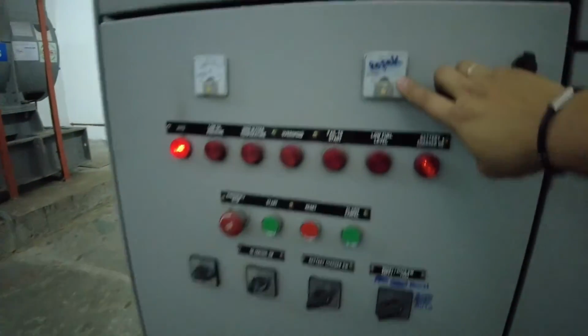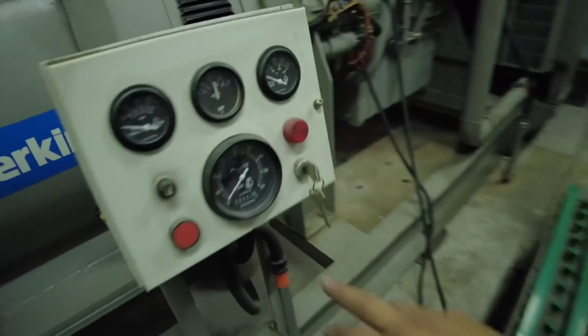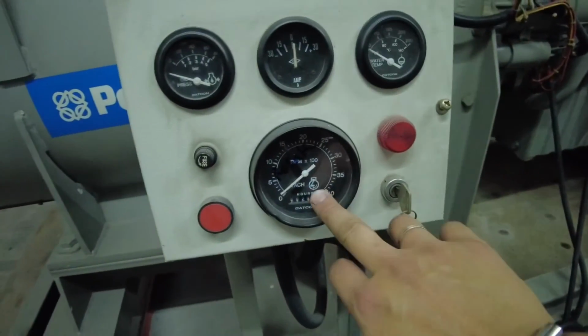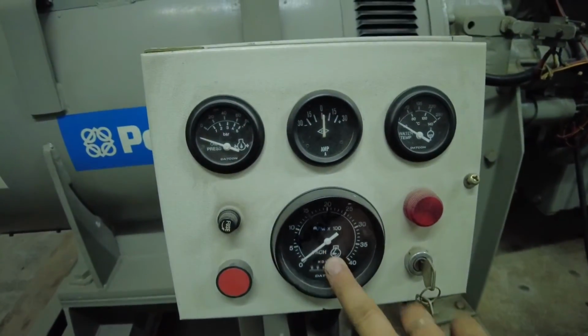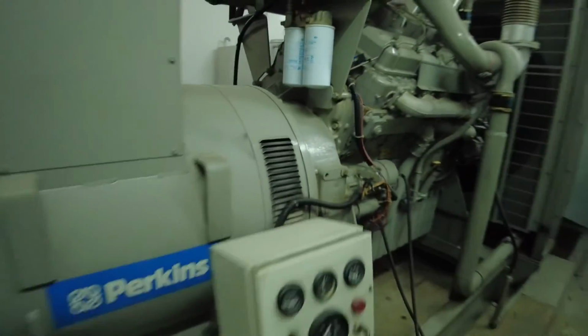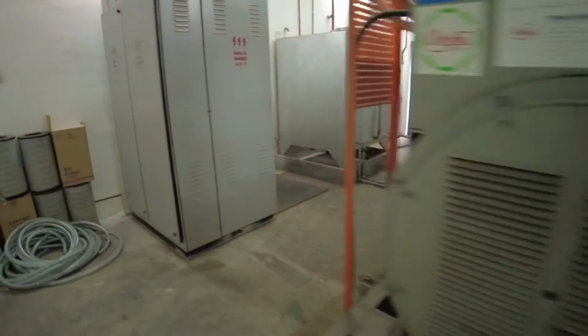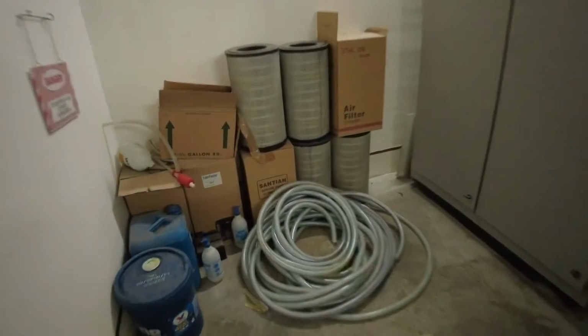After the genset stopped automatically, we found two items faulty. First thing is this voltmeter is faulty. And also this RPM meter is faulty. There's no reading coming up. Overall the rest is okay. Not much issue.